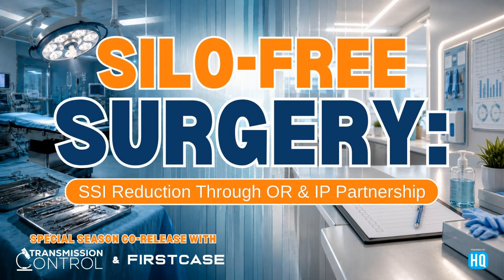They're taking a safety approach here to add additional steps to accommodate what is probably not in the IFU. So we saw that this is the entire process. We're definitely not doing ultrasonic cleaning in most of them. Sure. That's a huge area of opportunity. Yes. So we started bringing that on. Anything that's orthopedic, dental, ultrasonic cleaning is now a must. You cannot just say we don't need it. And so we do add that into the processing.